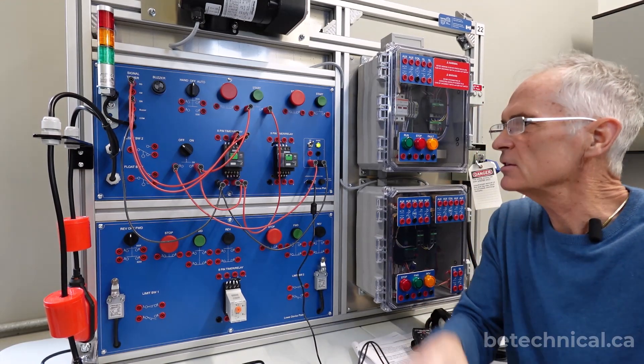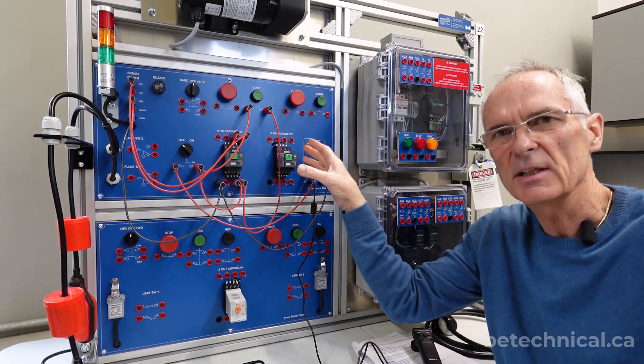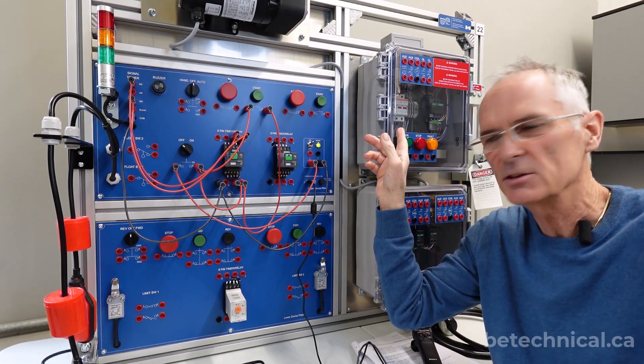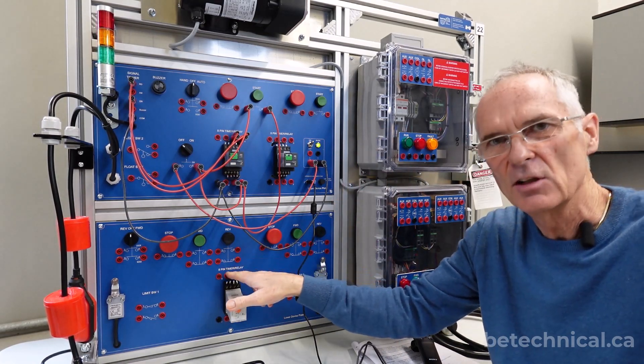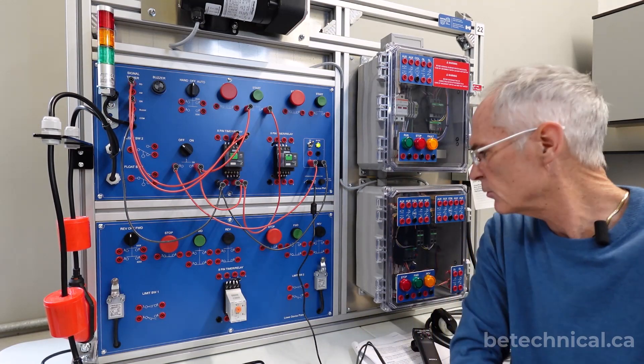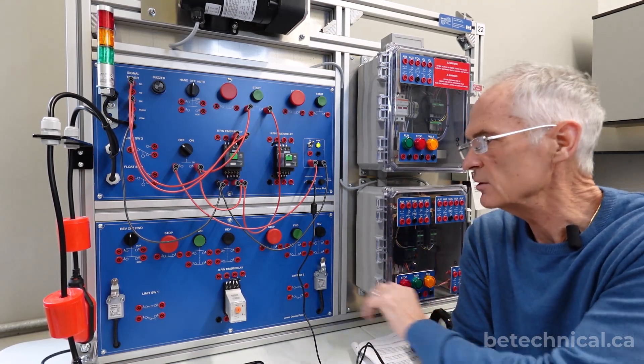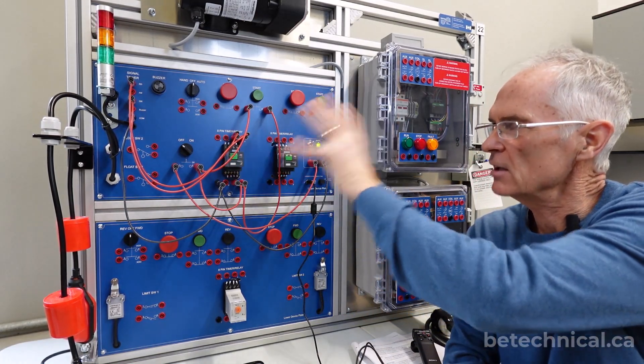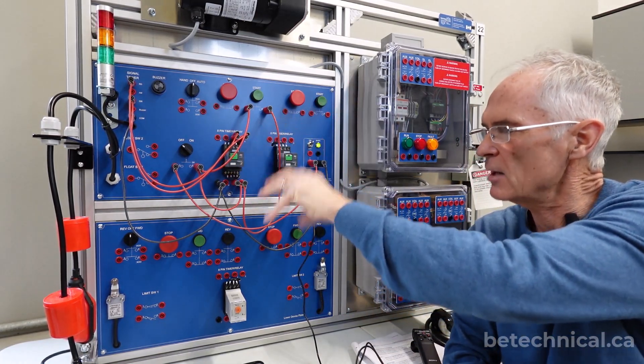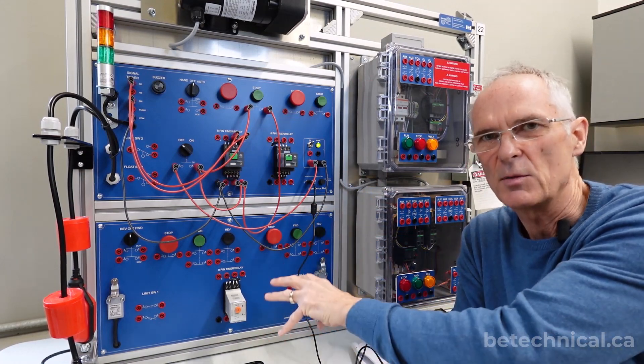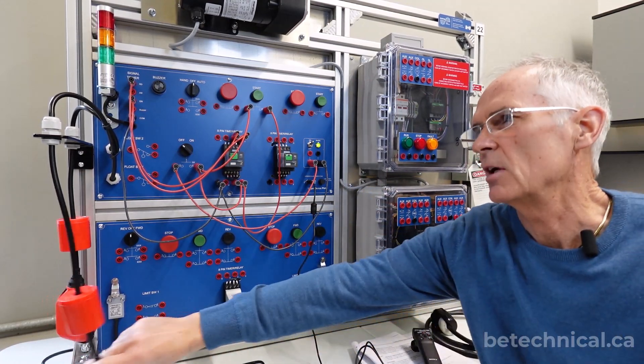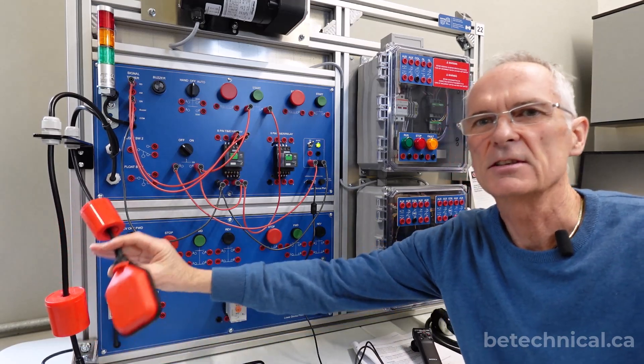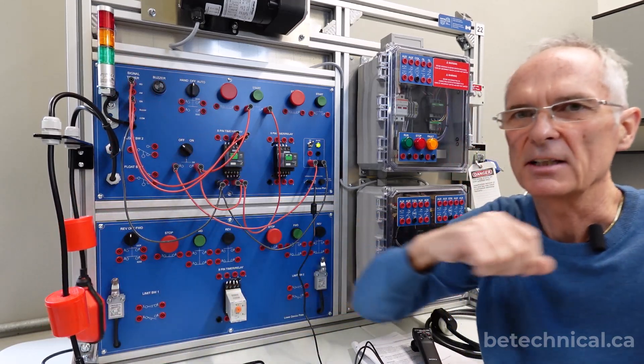The low voltage control section consists of an upper device plate which lines up with a non-reversing motor starter enclosure and a lower device plate which lines up with a reversing motor starter enclosure. Basically the devices are such that we have our non-reversing devices typically on the top and reversing on the bottom. For example, our float switches are on the top plate because typically we don't reverse a pump, we only control it in one direction.